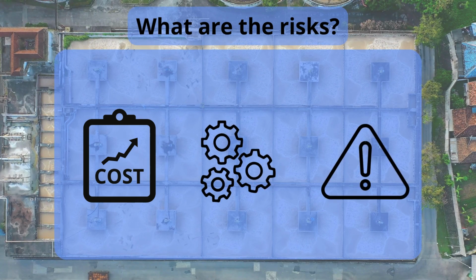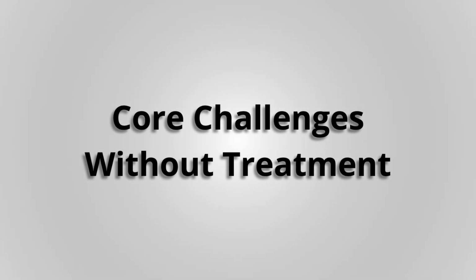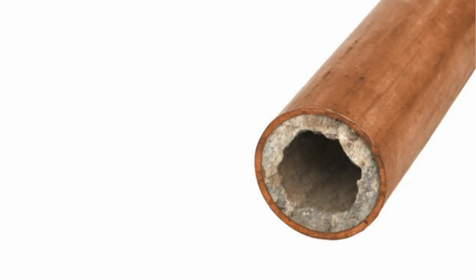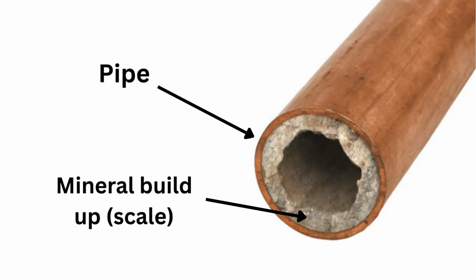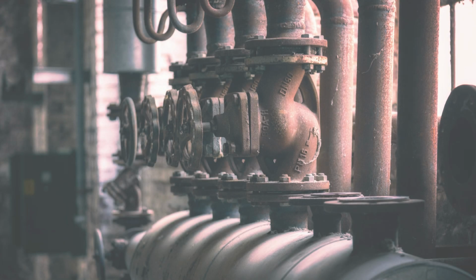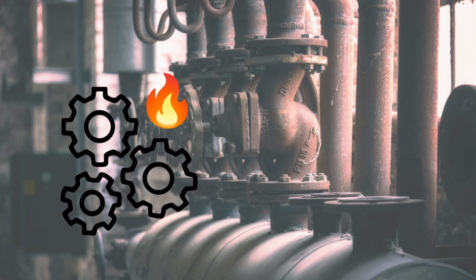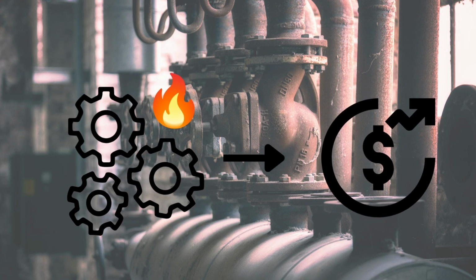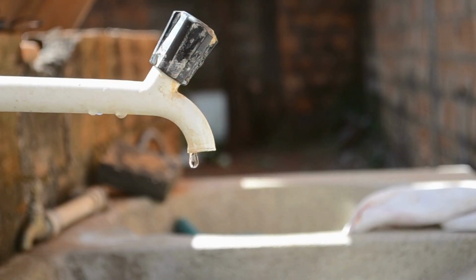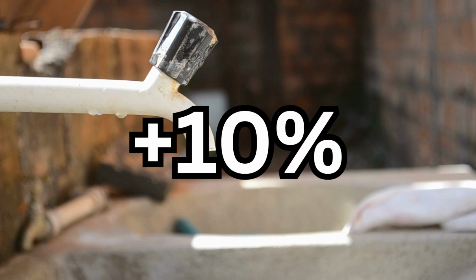What happens if water isn't treated? The risks show up quickly, and they're costly. Scale buildup is one of the most common problems. Minerals in the water harden on equipment surfaces, creating a layer of insulation. That means boilers and heat exchangers have to work harder, burning more energy and driving up utility bills. Even a thin layer of scale can reduce efficiency by 10% or more.